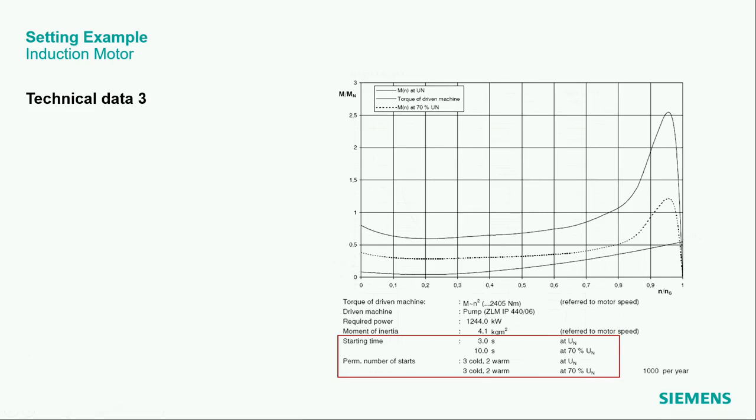If you make a little bit more calculations about the temperatures, then you will see it is a higher stress if you have the starts with a reduced voltage. The starting current is not that big, but the starting time is longer, and the starting time counts more in these calculations. That means if you want to use really the complete performance of the motor, you should go for these values at 70%.